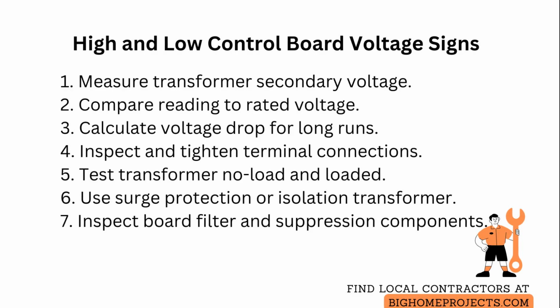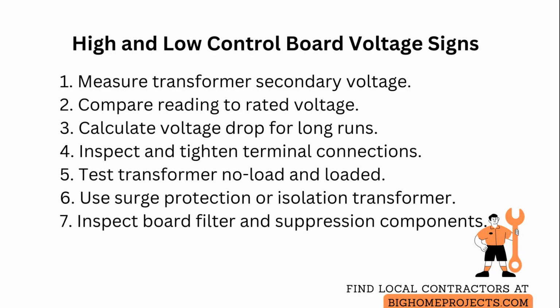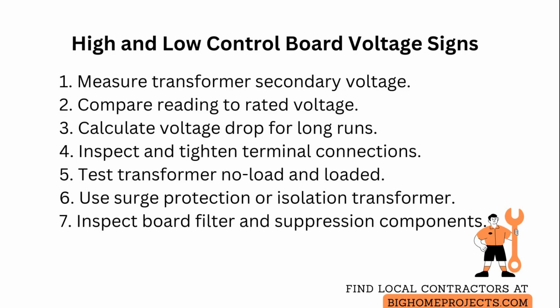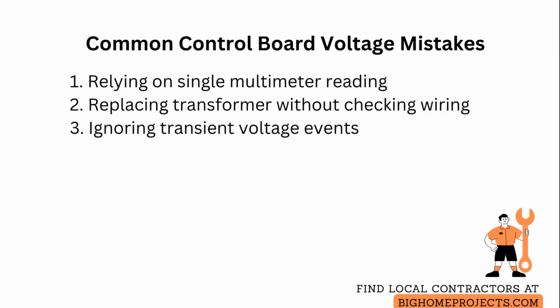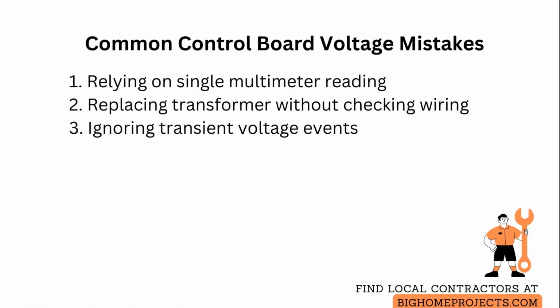When diagnosing control boards, also inspect the board's input filter capacitors and transient suppression components for bulging, discoloration, or cracked solder joints, because failed filter parts can allow mains transients or create internal short paths that distort the apparent terminal voltage. Common mistakes include assuming a single multimeter reading proves component health.